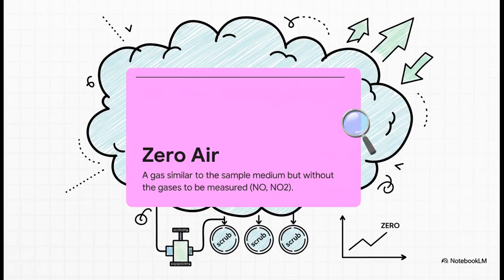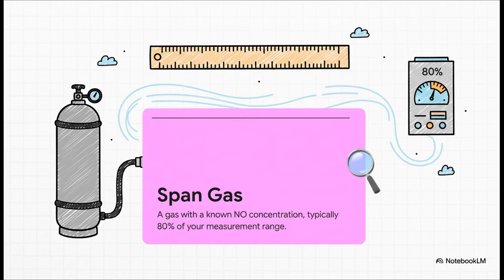Let's talk about that baseline. What is zero air? Think of it like a perfectly clean slate. It's air that's been scrubbed clean of the very things we're trying to measure. This is how we teach the analyzer, hey, this is what nothing looks like. It's our 0 point. And then we have our yardstick, the span gas. This stuff has a super precise, known concentration of nitric oxide in it. We usually pick a concentration that's about 80% of the instrument's full range. This sets the top end of our measurement scale, making sure we're accurate all the way across the board.